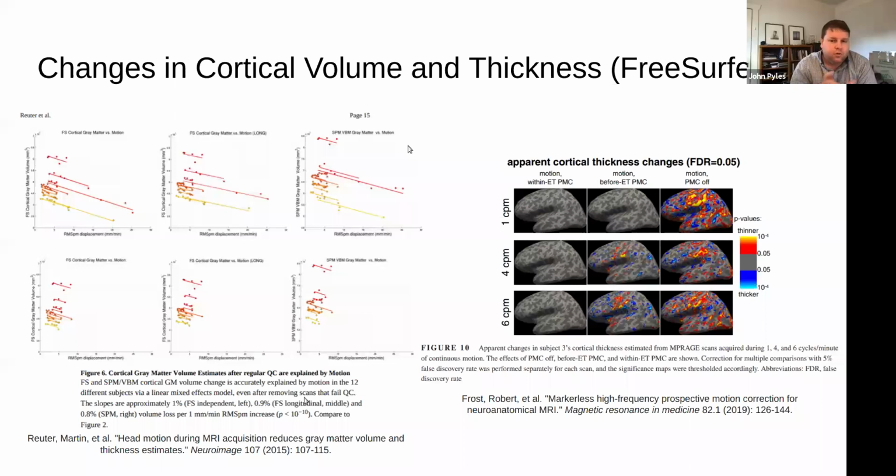Following up on this, since you've worked with these systems, Paul, one of the continuous concerns, and this is not the non-rigidness inside the brain, but just the skin versus the skull and the brain, right? The trackers, and I've heard that with KinetiCor it's better to attach it to the teeth versus the bridge of the nose, because your skin moves, and especially when your participant's padded in the coil, you have pads which are pulling their skin.